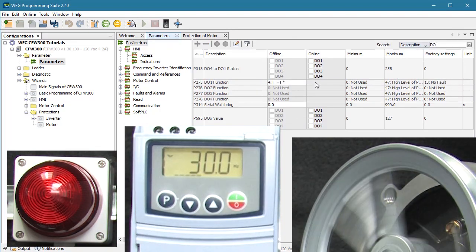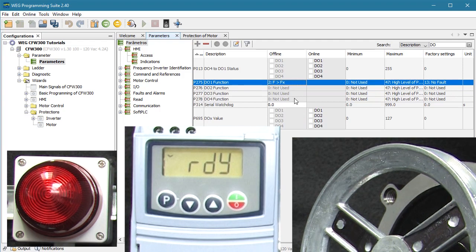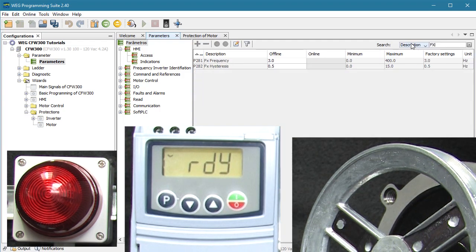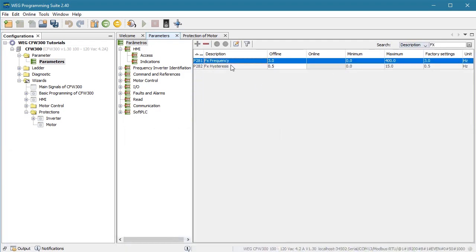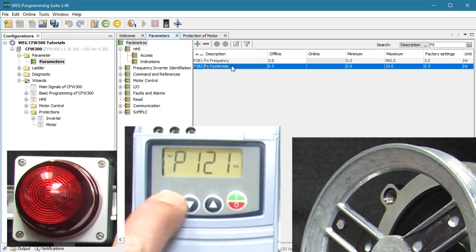We can also have the digital relay output turn on when the frequency gets above some value we set, which WPS calls FX. If we search on FX, we see that we can set both the value and the hysteresis. FX is the value or threshold we want to exceed. The hysteresis says you must exceed the value by this much for the light to turn on and this much for it to turn back off again — so if your frequency output is bobbling around a little bit due to load changes, it won't keep tripping the indicator.